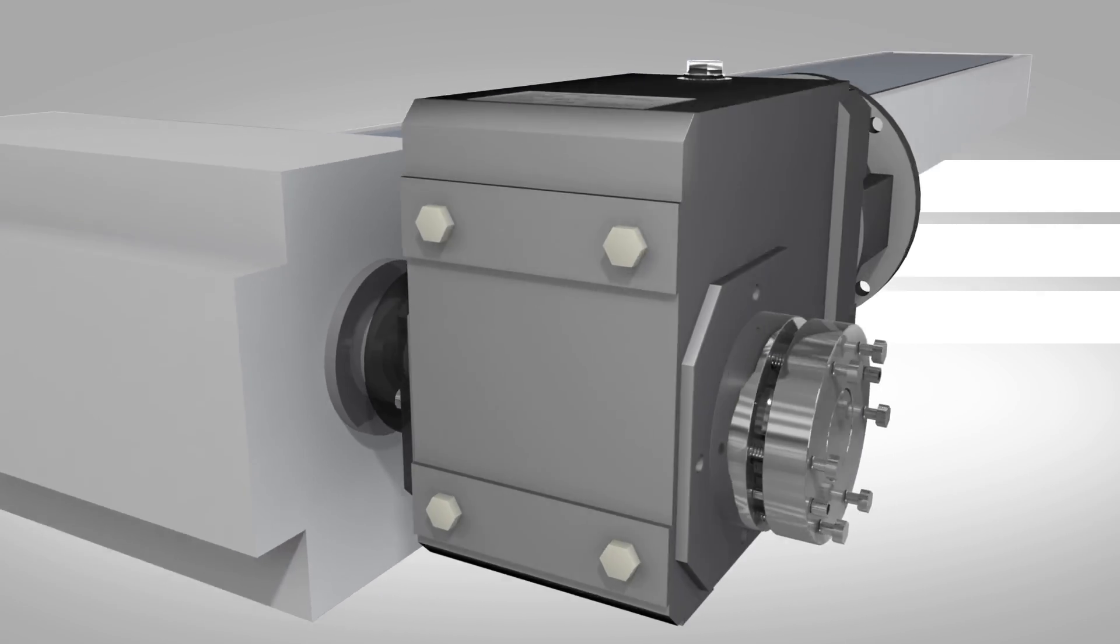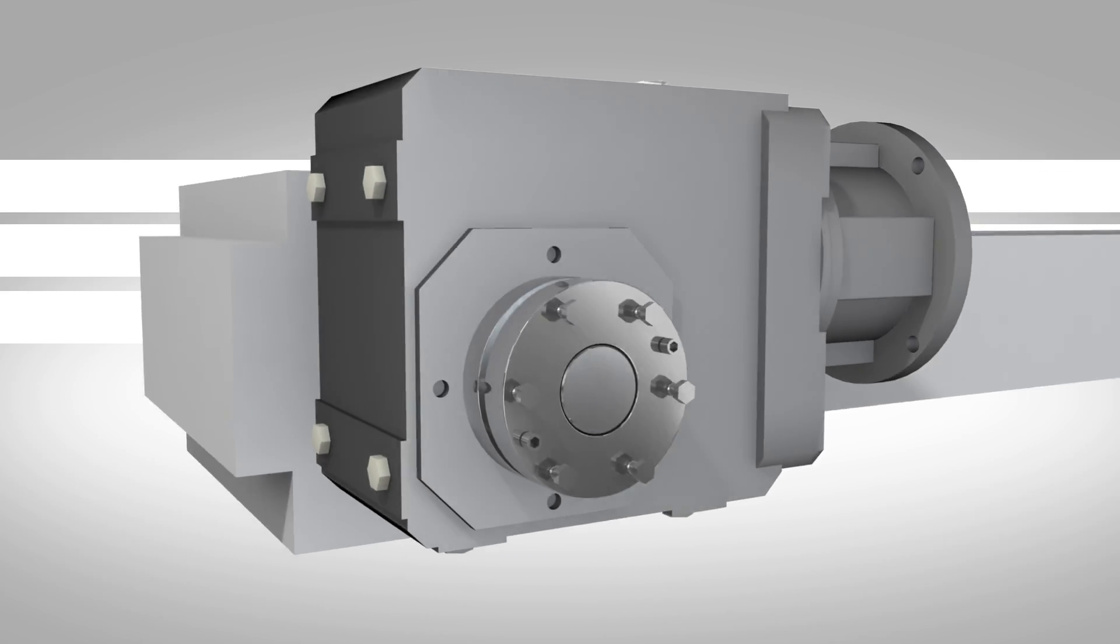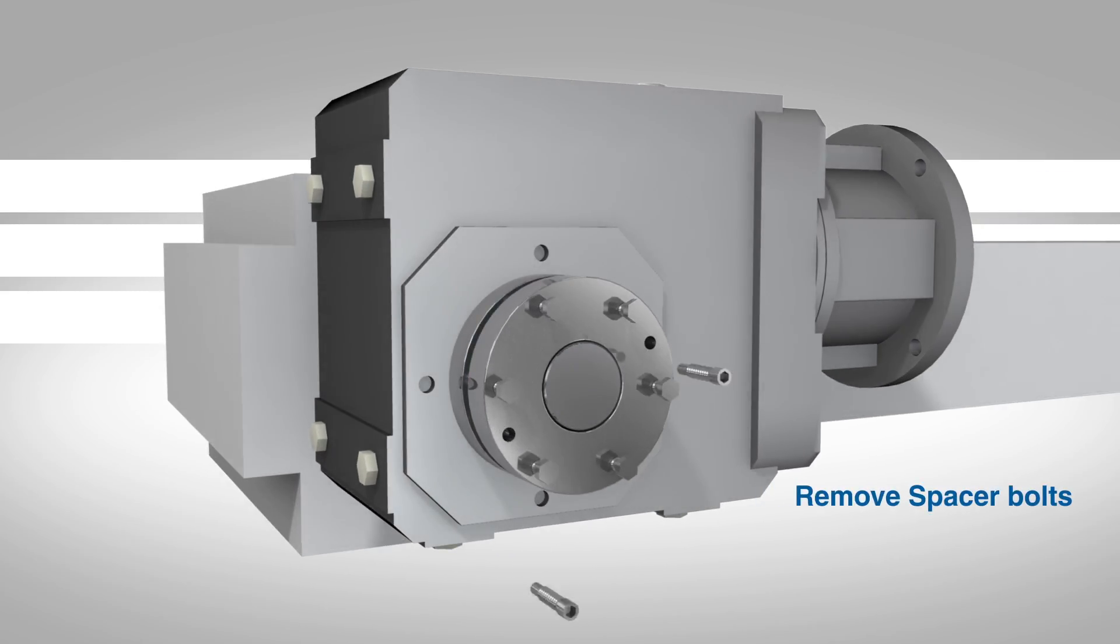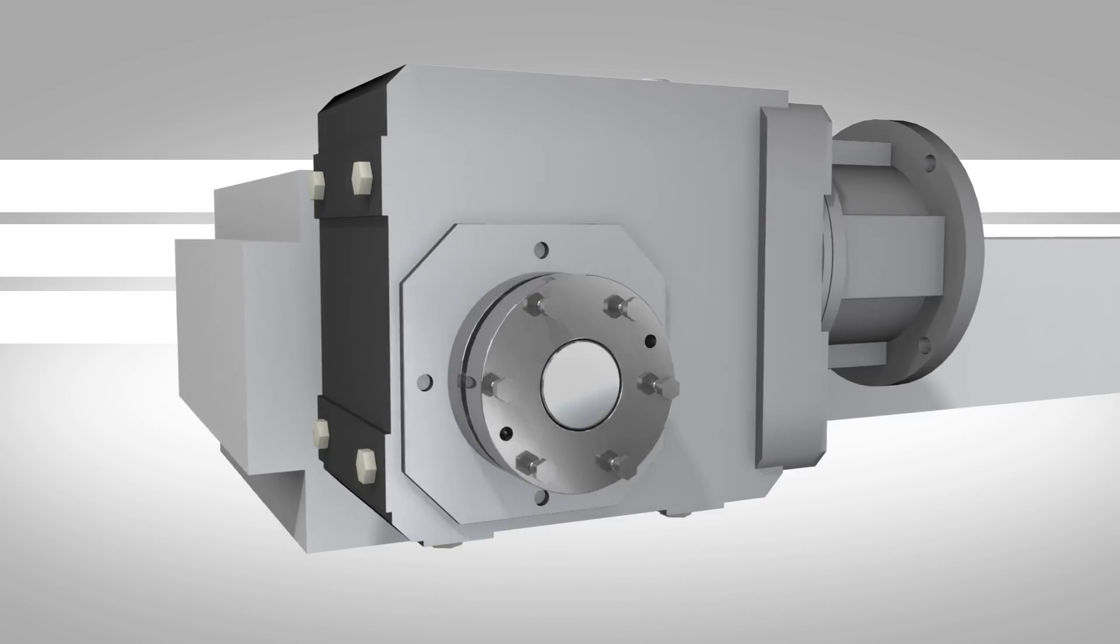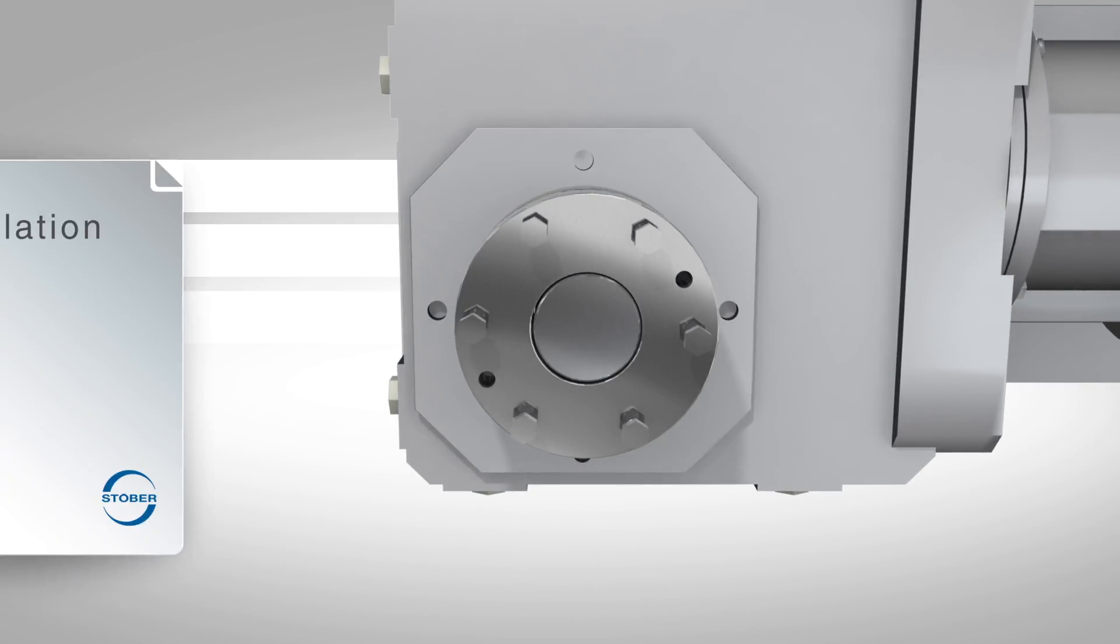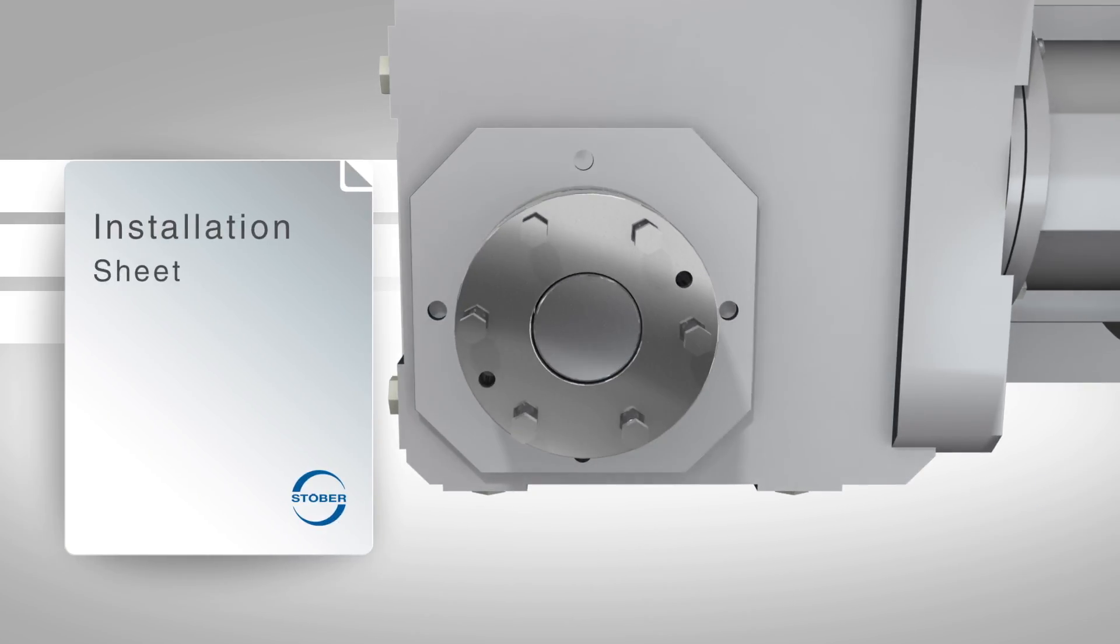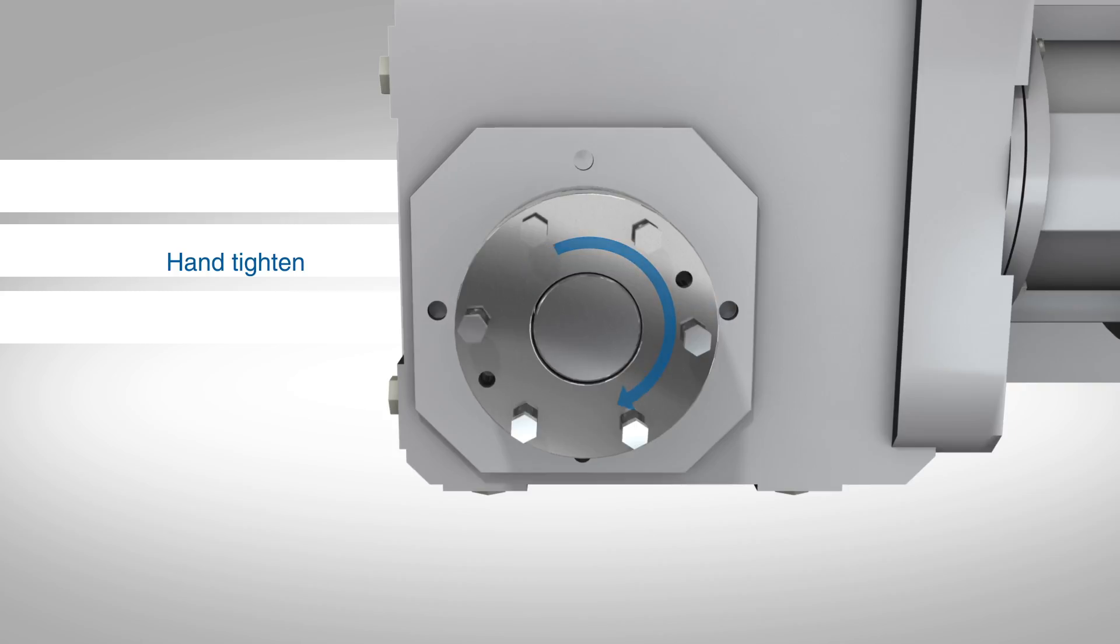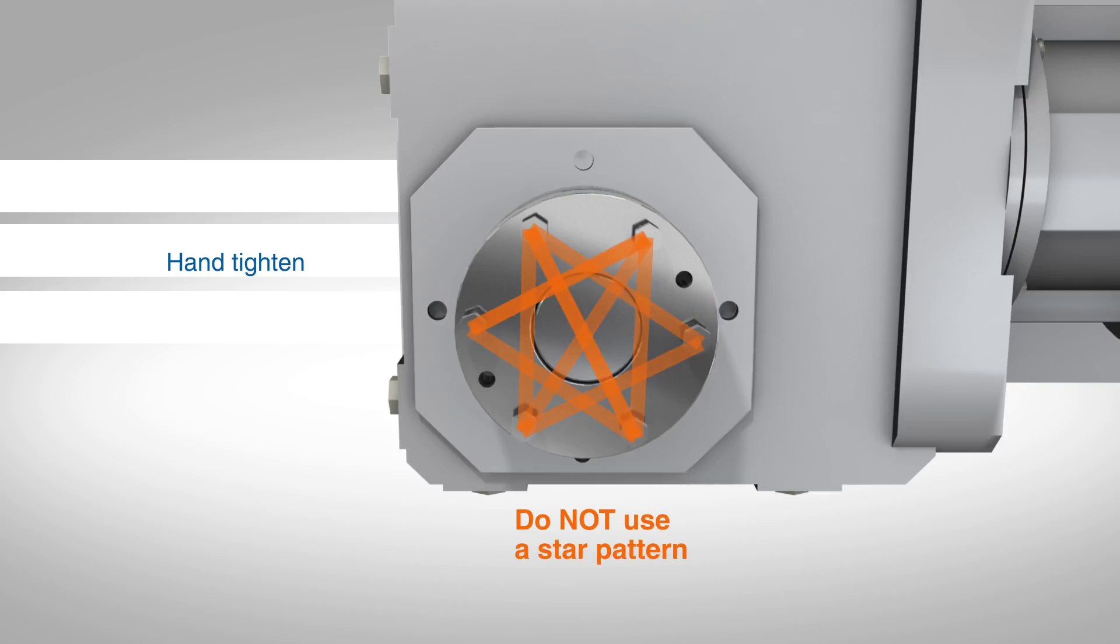Once the reducer is in position, remove the spacer bolts from the support side bushing assembly. Tighten the hex head bolts on the clamp side bushing assembly to the torque shown in table one of the installation sheet. Begin by tightening the bolts by hand using a circular pattern. Do not use a star pattern as this will cause the gearbox to wobble or move on the shaft excessively.